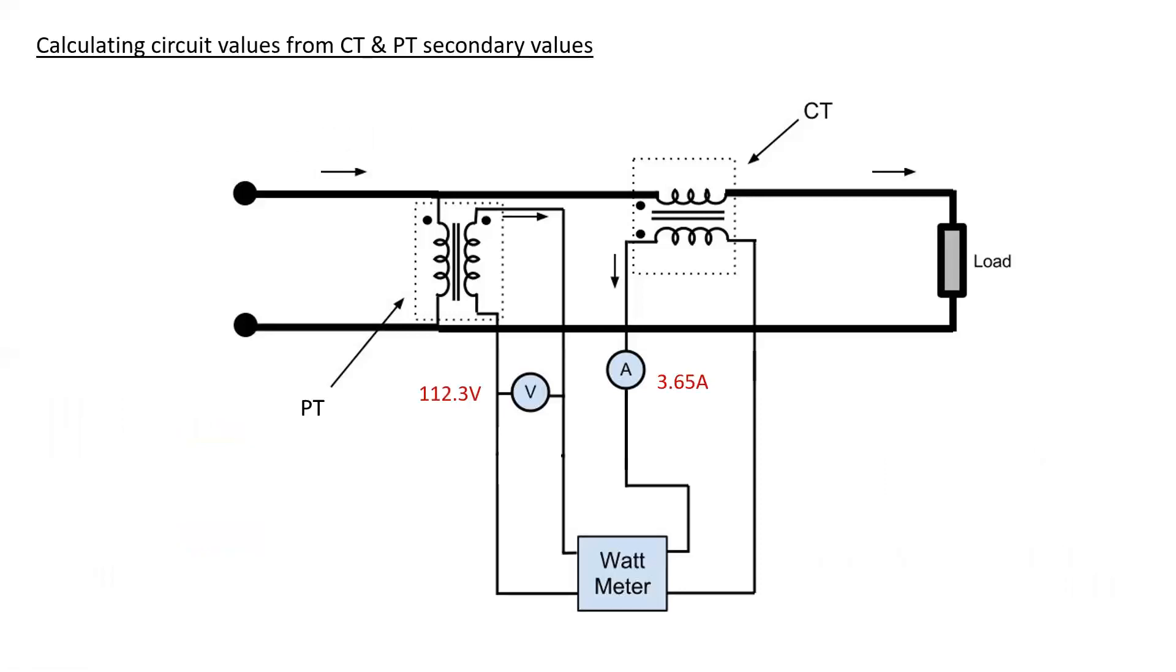Let's try another one. This time, what we're going to do is calculate circuit values from the CT and PT secondary values. So I have a voltmeter with 112.3 volts, and I have an ammeter with 3.65 amps. I'm using slightly different PT and CTs. So the PT is 4160 to 120, and the CT is 200 to 5. So let's break these down to their ratios. So the PT is 34.66 to 1, and the CT is 40 to 1.